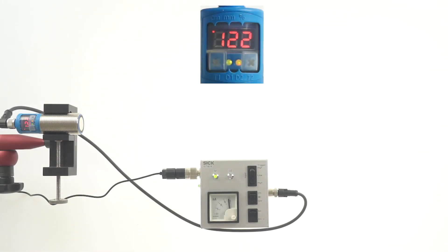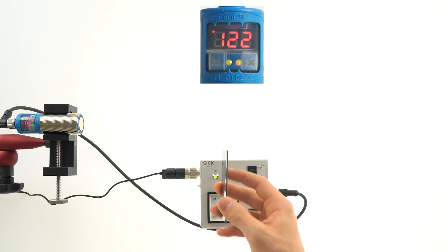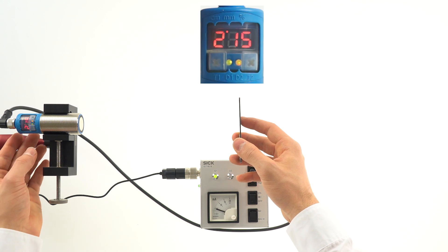For the scaling of the analog output, position any ultrasonic reflecting object, for example a business card, in front of the sensor at the desired near distance to teach the 4 milliamp value.